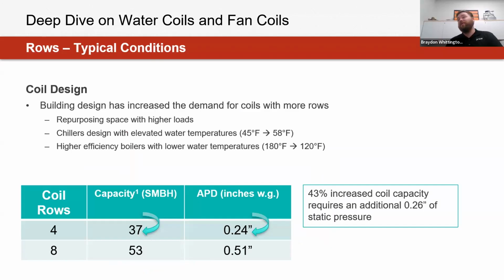In terms of trends in how many rows are utilized within the industry, we're starting to see higher numbers required for both terminals and fan coils, for both heating and cooling conditions. The reason is that chiller designs are running at much higher elevated temperatures through that coil. And with high efficiency boilers or heat pumps, we have lower water temperatures through the heating side. With tighter restrictions, either warmer cold water or colder hot water going through the coil, it's harder to achieve the same capacity we've seen for that coil. We'll have a really good retrofit example to go over in a little bit. But now in a lot of applications we're having to increase the number of rows on a lot of this equipment within the schedule.